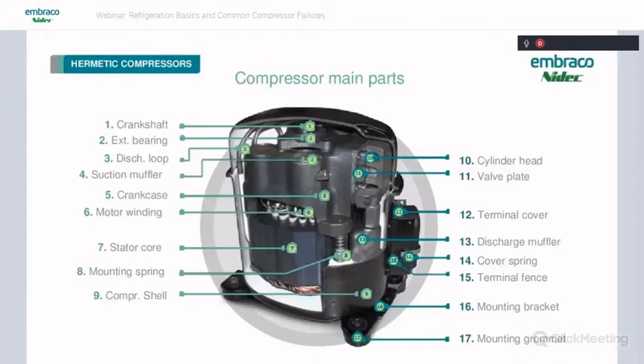So this slide just shows an internal view of a basic hermetic compressor. You can kind of see how the components are laid out here. We have the motor, the stator core that sits horizontally, and the shaft that goes up in the center, going vertically up through the rotor to the reciprocating assembly, which is sitting horizontally. So you can kind of see the discharge muffler, suction muffler. The cylinder head is right here. Most all of our compressors, actually all of our compressors right now, are single cylinder. So this is pretty much going to be the layout of all the compressors that we have today.